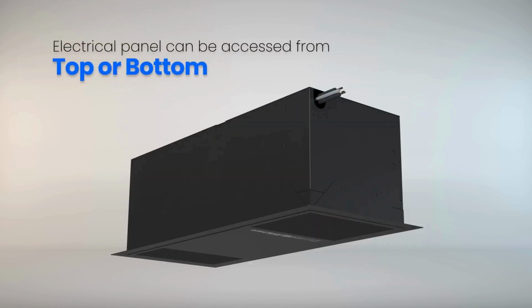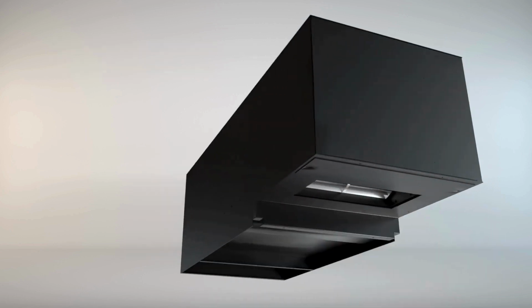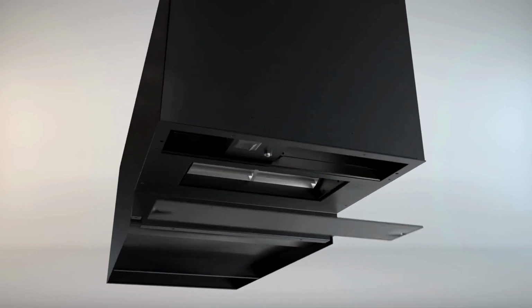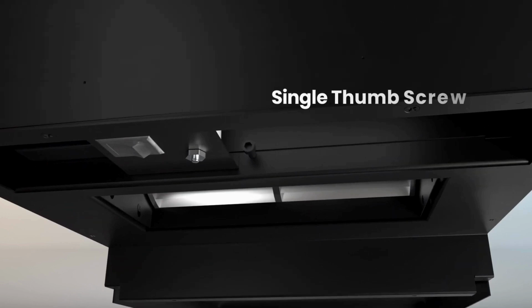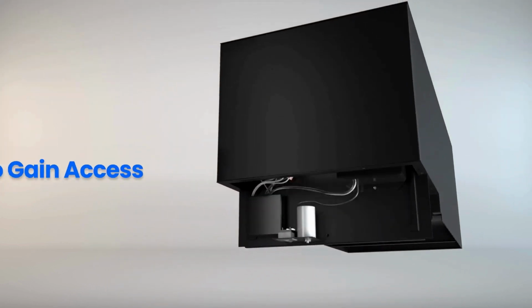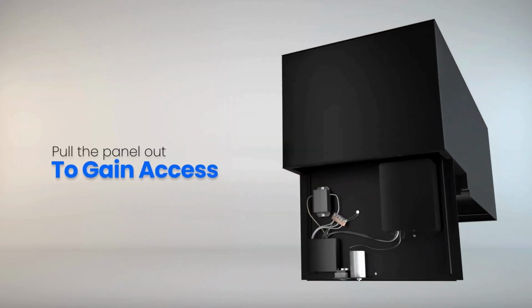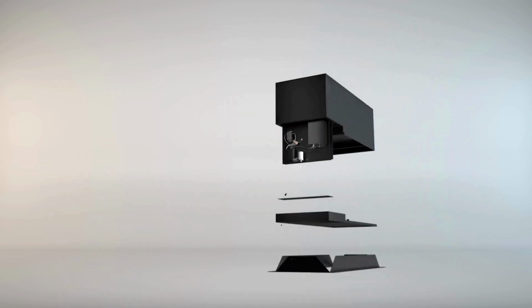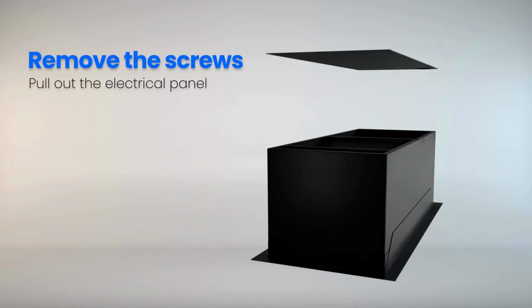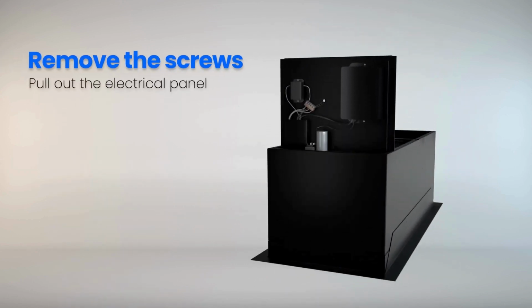The electrical panel can be accessed from the top or bottom of the unit for ease of installation and periodical maintenance. When accessing from the bottom, remove the grill. The electrical panel is held in place by a single thumb screw. Remove the thumb screw and pull the panel out to gain access to the electrical components. For access from the top, remove the screws and pull out the electrical panel.